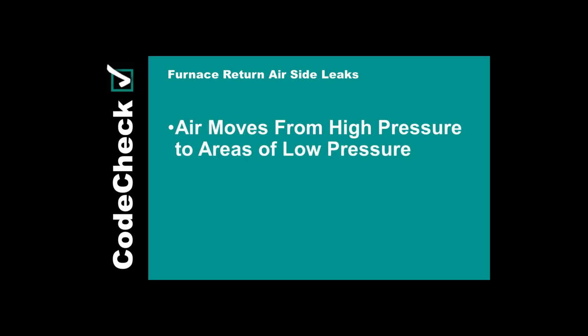Air always moves from high pressure to low pressure. So if you have a return air with a fan in operation, that area is significantly negative in air pressure and will draw air from any place it can around it, including the enclosure and the furnace above.